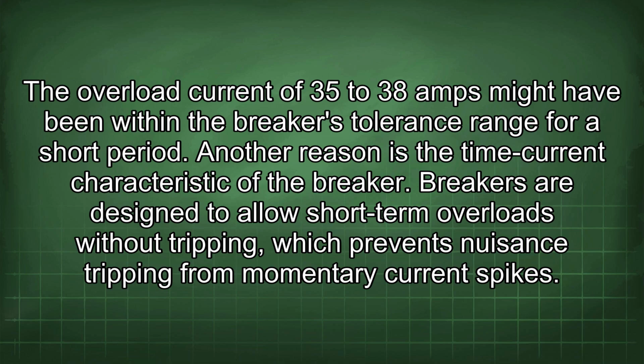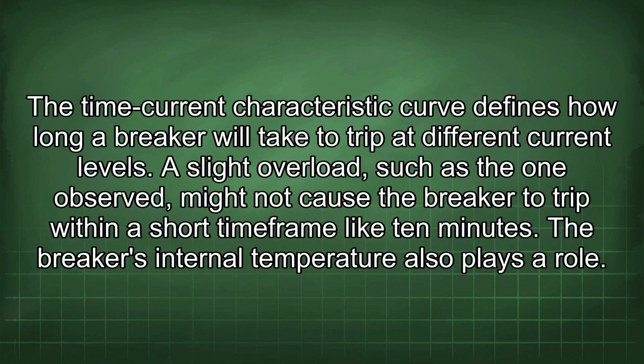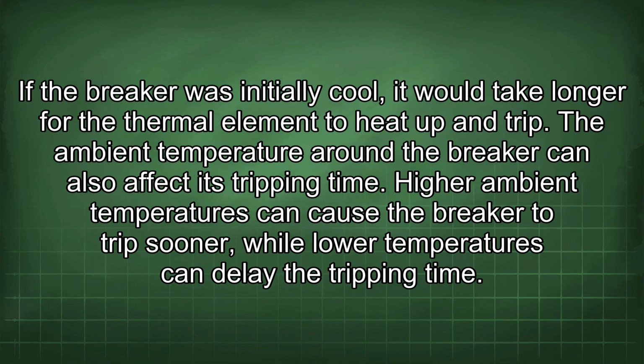Breakers are designed to allow short-term overloads without tripping, which prevents nuisance tripping from momentary current spikes. The time current characteristic curve defines how long a breaker will take to trip at different current levels. A slight overload, such as the one observed, might not cause the breaker to trip within a short time frame like 10 minutes. The breaker's internal temperature also plays a role. If the breaker was initially cool, it would take longer for the thermal element to heat up and trip. The ambient temperature around the breaker can also affect its tripping time. Higher ambient temperatures can cause the breaker to trip sooner, while lower temperatures can delay the tripping time.